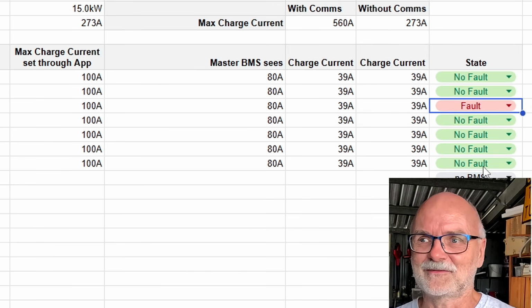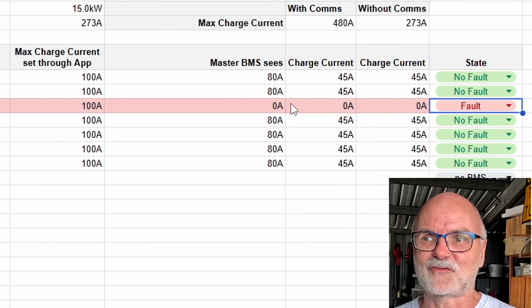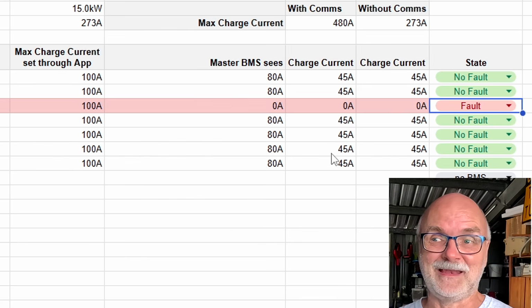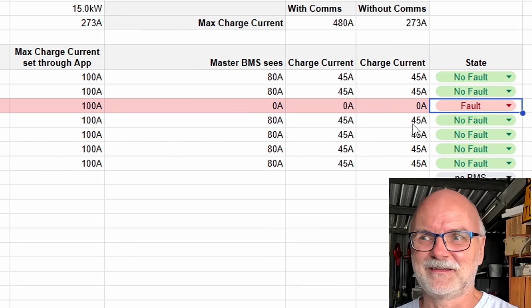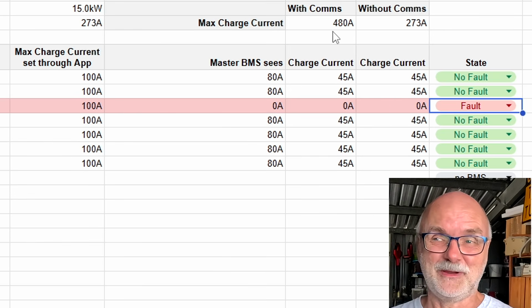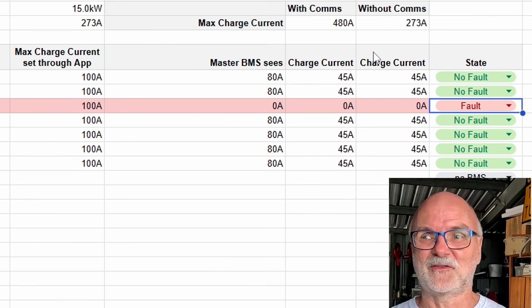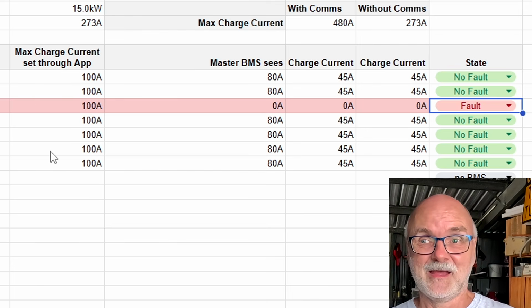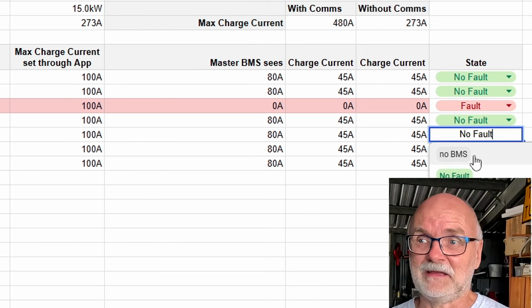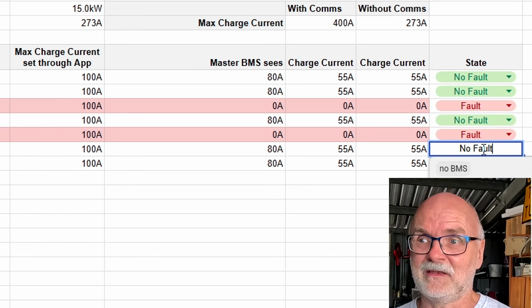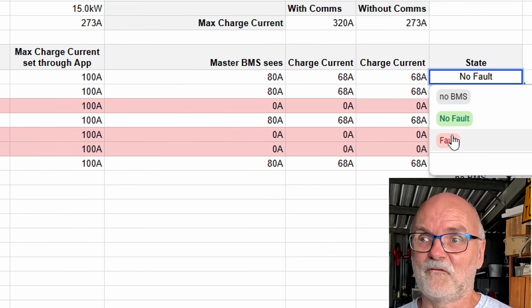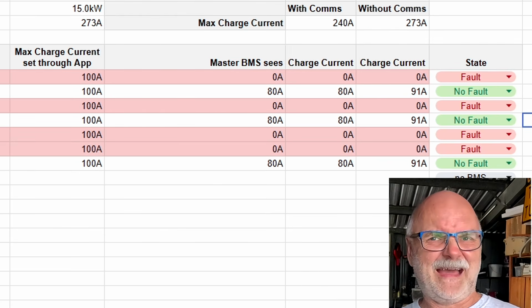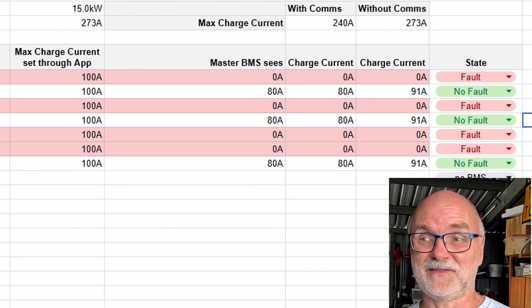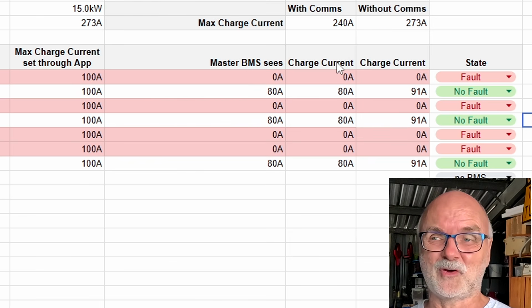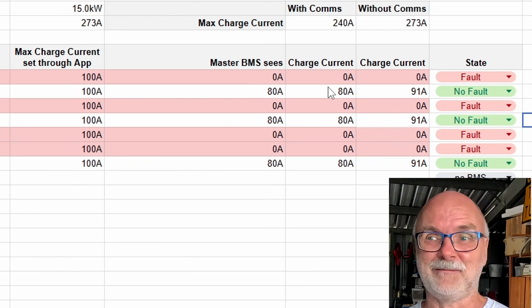So our battery here has this over temperature protection again, drops out. Charging current into the remaining batteries increases by 6 amps. So that is basically nothing. With communication, without communication, makes no difference. We are far under these 100 amps we have set per BMS. Even if I fault another BMS here and another one and a fourth one as well. Very unlikely scenario, I've got 4 faulty BMSs in my system. But still, you can see with communication, 80 amps into the remaining batteries. Same as with all the batteries online.